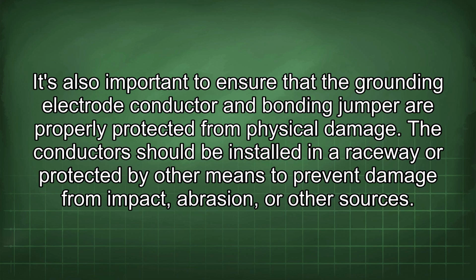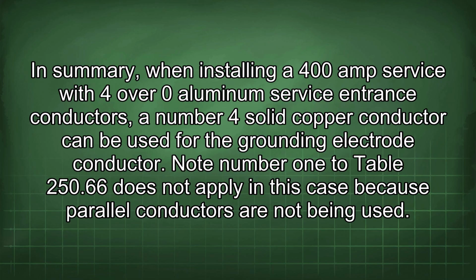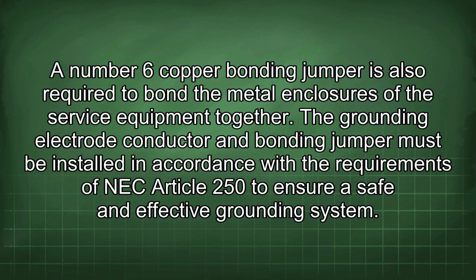other sources. In summary, when installing a 400 amp service with 4/0 aluminum service entrance conductors, a number 4 solid copper conductor can be used for the grounding electrode conductor. Note number 1 to Table 250.66 does not apply in this case because parallel conductors are not being used. A number 6 copper bonding jumper is also required to bond the metal enclosures of the service equipment together. The grounding electrode conductor and bonding jumper must be installed in accordance with the requirements of NEC Article 250 to ensure a safe and effective grounding system.